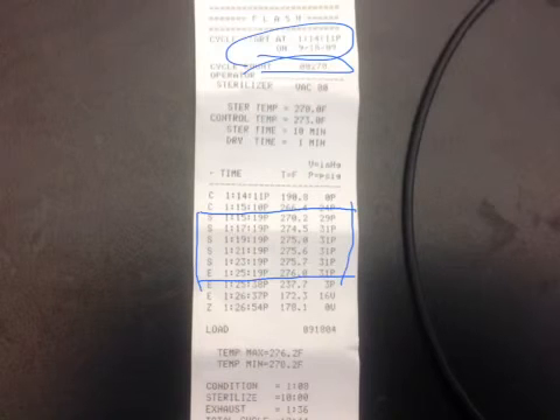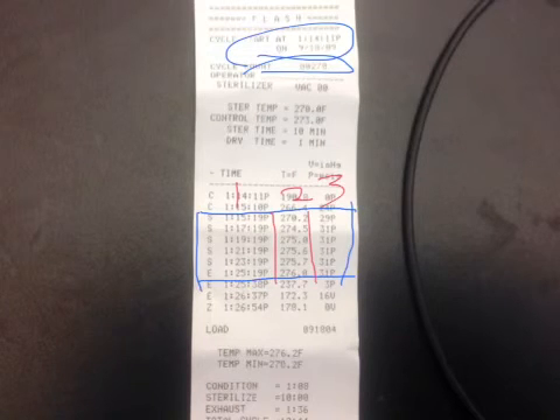So let's look at our three columns. In column one, we see that we've got 10 minutes difference. It's 1:25:19 minus 1:15:19. In column two, we can see that it stayed above 270 degrees. In column three, we can see that it stayed above 27 psi. So this cycle is good for a 10-minute cycle. So any instrumentation that needs a 10-minute cycle, this has achieved that.